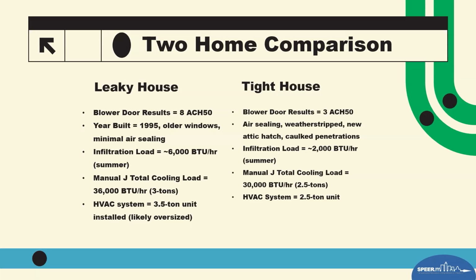So I know the audience is probably asking, but that's comparing older homes to new homes. That's true. But there's a lot of weatherization that's now happening around Texas and Oklahoma that's actually starting to shrink that air leakage and infiltration. And I know they test in and test out. Requiring someone to have that data when you have an HVAC system changed out would be a good thing. So not verifying the older homes, the newer homes that are built, and not knowing how tight or loose they are, we just talked about it, significantly challenges the sizing requirements for HVAC.